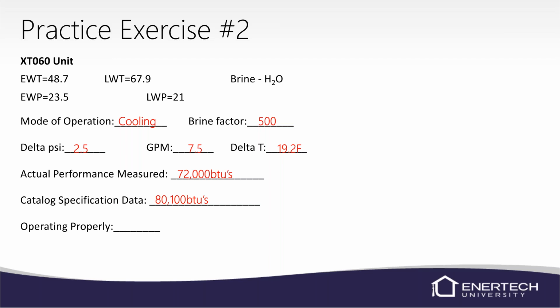In a situation like this, it could be that the heat exchanger is starting to get a little bit scaled up and it's not necessarily ready to be cleaned yet, but it will be next year. So that's probably what I would look at. We actually have a way also, I'm not going to get into it today. It'll be something that we cover in troubleshooting and startup in 3 or 4 weeks. But we do have a calculation that we can use to figure out if a heat exchanger is scaled up. We can take some pressure ratings and some temperatures and do some math. So that is available if you ever want to figure out on an open loop if your heat exchanger is starting to scale up. We'll cover that at a further training.